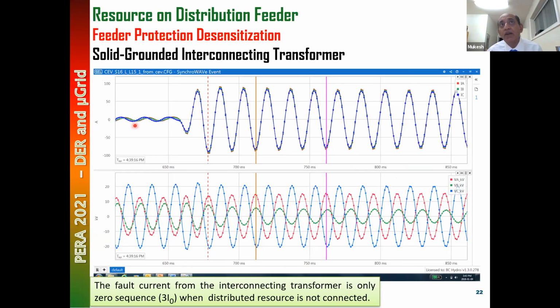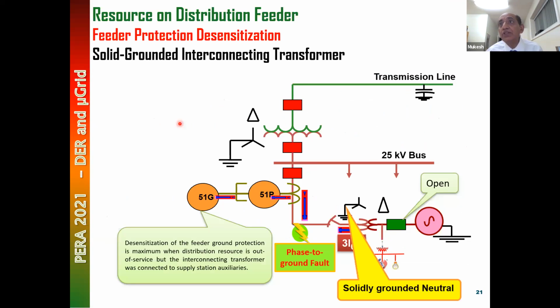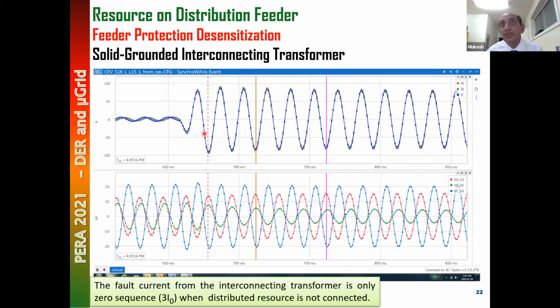Look at the fault. Before the fault, there was very little current going. It was a residual current. And as soon as the fault happened, there was a lot of current going here. Sorry, I apologize. The fault was here, and as soon as this breaker opened here, for some other reasons, there was an all zero sequence current.